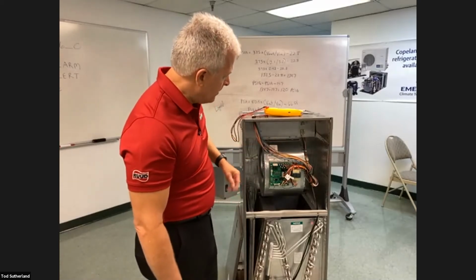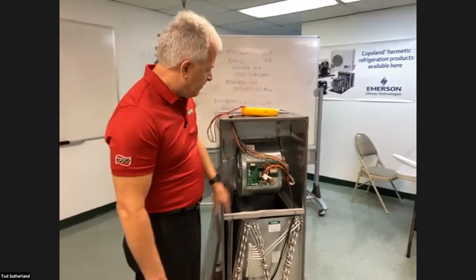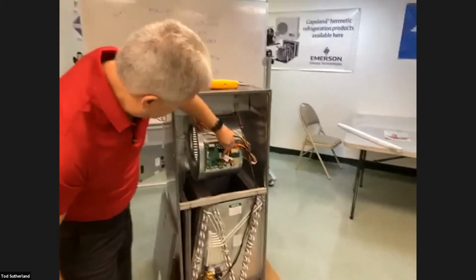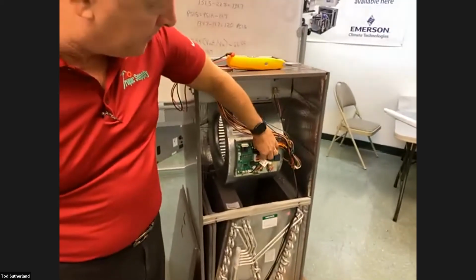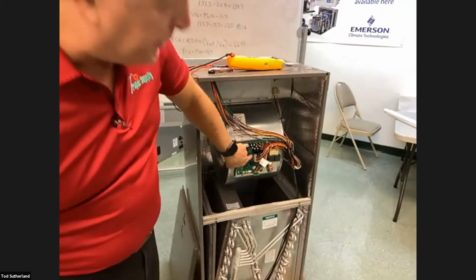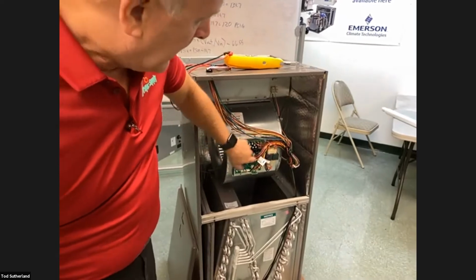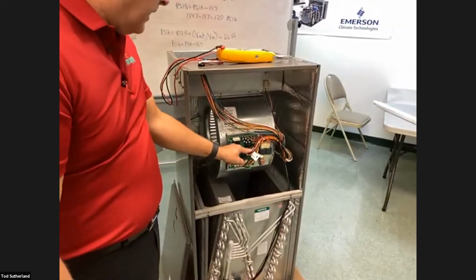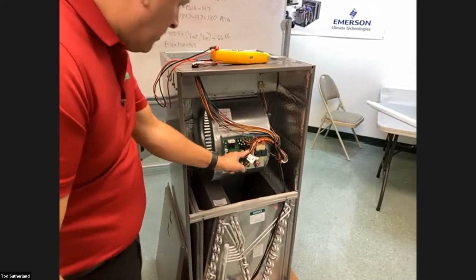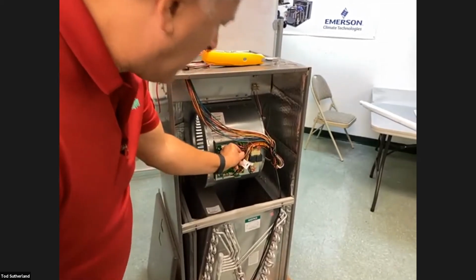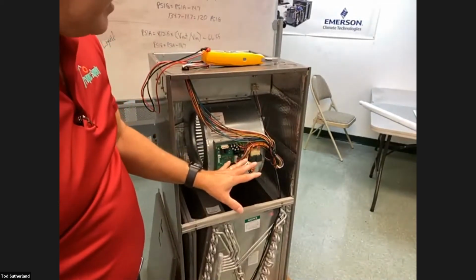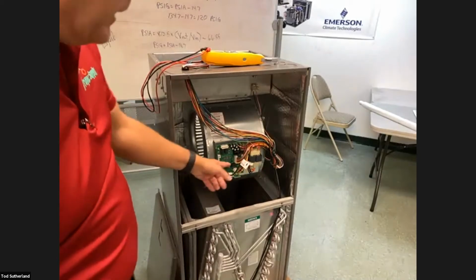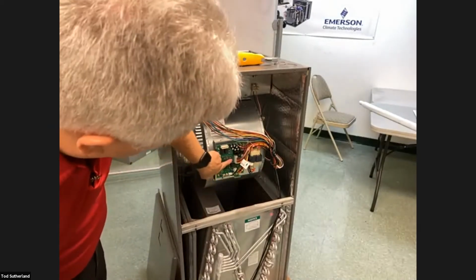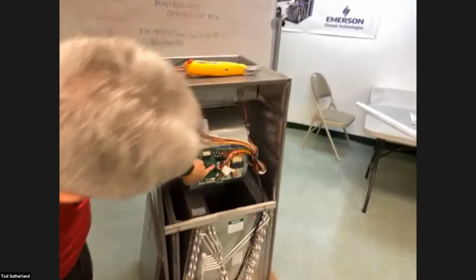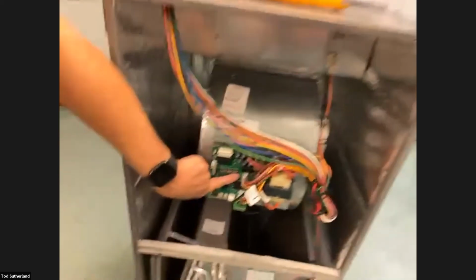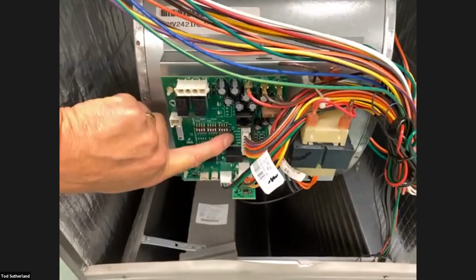So when you're connecting your 4 wires here, the top 2 wires on this plug are a brown wire with a white tracer and a purple wire. Those are your 2 communicating wires, E1 and E2. Then off of the other plug, you're going to have your red wire for R and your solid brown wire for common. Those are the 4 wires you're going to be using. In addition to that, you're going to be using 2 extra wires here. The next 3 wires down are labeled AUXC, AUX1, and AUX2.